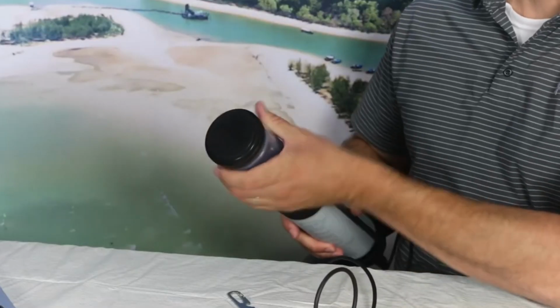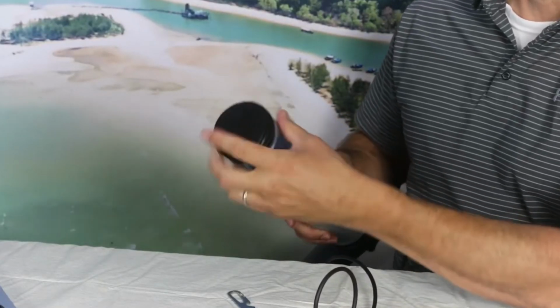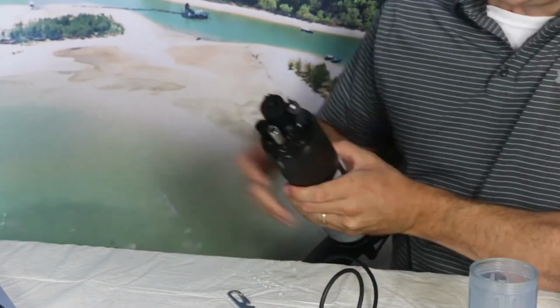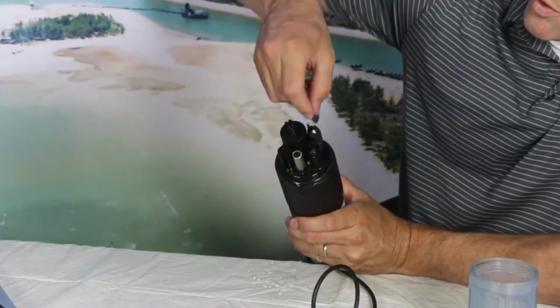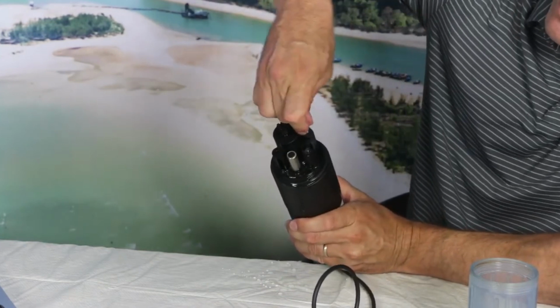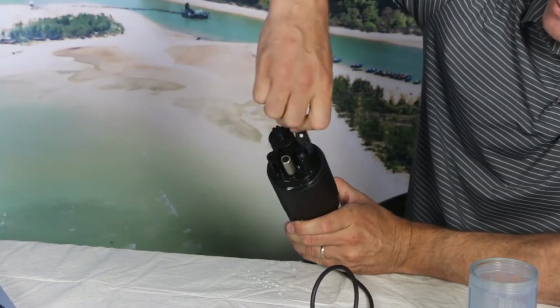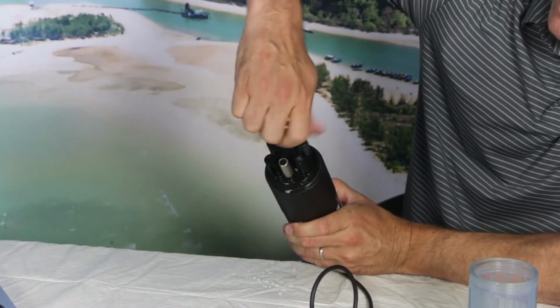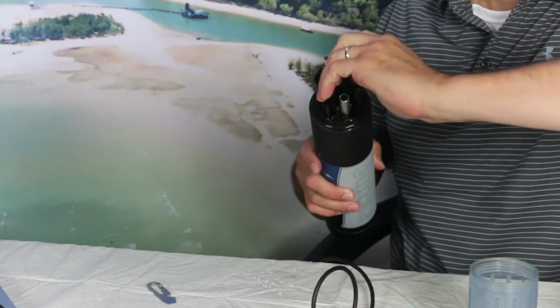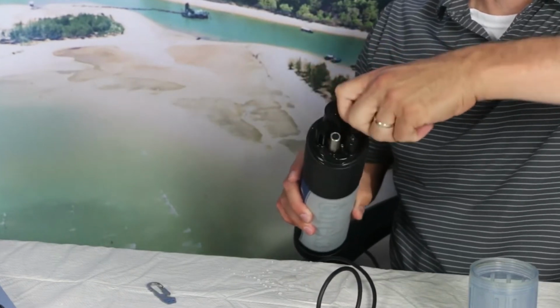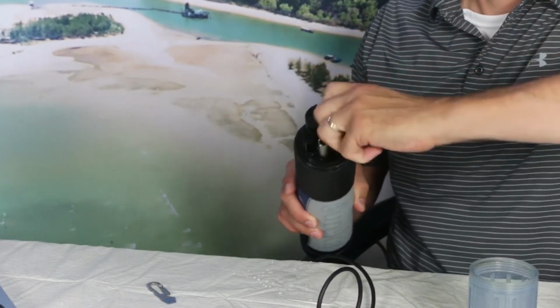If you haven't replaced your reference electrolyte recently, now is the time to do it. This is a good time to replace electrolyte solution before you calibrate your pH sensor. So to replace our reference electrolyte, we're going to remove the calibration cup. You can use a coin or a flathead screwdriver to remove the reference cap. And we're just going to dump out the solution that's in there and replace it with new solution.